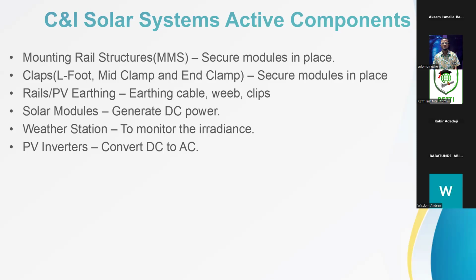What I mean by DC to AC ratio is this: if your solar system is 300 kilowatts peak, for your PV inverter, we have different sizes. We have the one of 50 kilowatts, they even have smaller ones, but for this brand we have 50, we have 100, we have 150. But when you have a system that is less than 1 megawatt, or let's say less than 500, please just go with 50 kilowatts. Because if I have a system of, let's say, 400 kilowatts, I might say, okay, because I want to reduce the space, let me use 4 PV inverters of 100 kilowatts. That is 4, and that is 400.